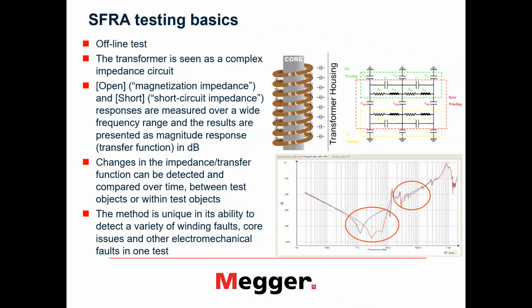What we can do with this complex impedance of the transformer, we can make a measurement on open windings, we can make a measurement on short circuited secondary windings, and make a measurement of attenuation in a wide frequency range, and see what the response of the transformer winding is. If we see changes in current measurements compared to previous ones, then we can conclude that there may have been some changes introduced in the test object, and if we can exclude test setup issues, then we certainly need to look into the measurement closer and see what has happened with the test object.